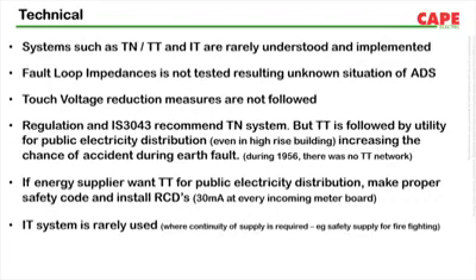Touch voltage reduction measures are not followed even in hospitals and explosive areas. CEA regulation and IS 3043 recommend a TN system, but TT is followed by the utility for public electricity distribution. This increases the chance of accident during fault. If the utility wants TT for public electricity distribution, make a proper local safety code and install RCDs, a 30 milliampere RCD at every incoming meter board. IT systems can be used where continuity of supply is required, for example, safety supply for firefighting.